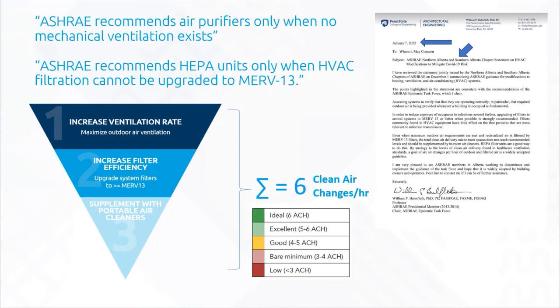I would ask for that first one. So let's say ASHRAE recommends only when no mechanical ventilation exists. So you have mechanical ventilation, but what if that mechanical system is only delivering 1 or 2 air changes per hour? It's definitely problematic. Or ASHRAE recommends HEPAs only if we can't upgrade to MERV 13. Well, again, what if we've upgraded to MERV 13, but there's only 1 air change per hour passing through that MERV 13? So we should just be careful.